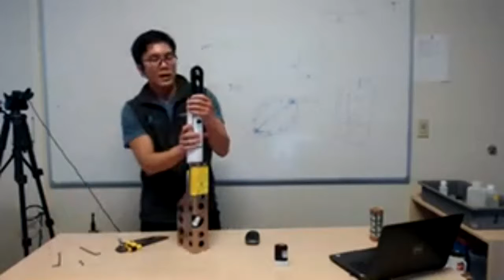Replacing the batteries on the HydroCAT EP is very similar to replacing batteries on an SBE 37. If you've done that before, we have these two screws on the sides here, I'm going to remove these. And we have this one screw on the top — you do not actually need to remove that. If you look closely, this screw is actually sitting on top of this little ramp, and that allows you to twist that screw; it goes up the ramp, backs off the end cap, and you can very carefully remove it.